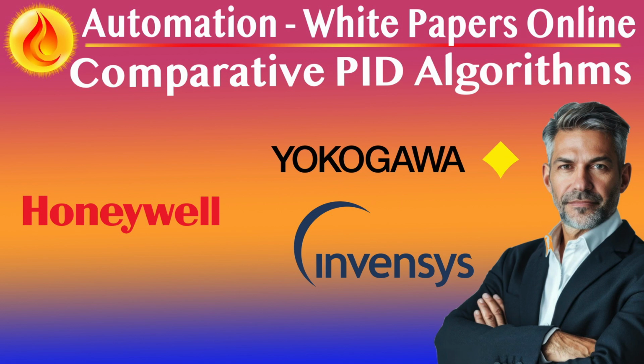Derivative action and filtering. Derivative behavior is one of the most differentiated aspects between these platforms. Honeywell uses implicit derivative filtering, where increasing the D value automatically increases internal filtering. This approach limits high-frequency noise amplification and simplifies configuration, especially for users less familiar with frequency domain behavior.